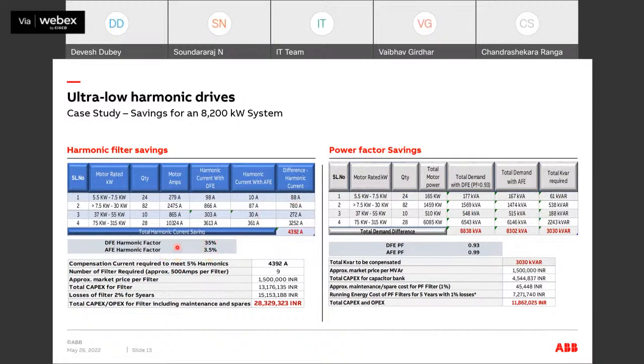So when we calculated the difference between the harmonic currents of these two technologies, we see that for the 8.2 megawatt load, we have approximately 4,400 amps which we need to reduce using harmonic filters. Considering an approximate calculation of 500 amps per filter, we require 9 filters. When we take the approximate price per filter and multiply it, there will be a requirement of 13 million, which is going to be added as capex when we buy a diode front-end drive.